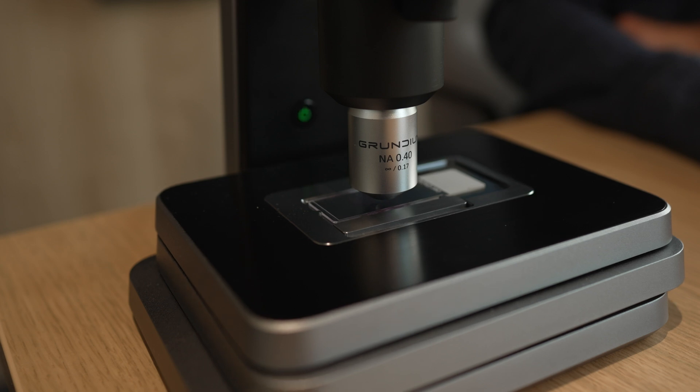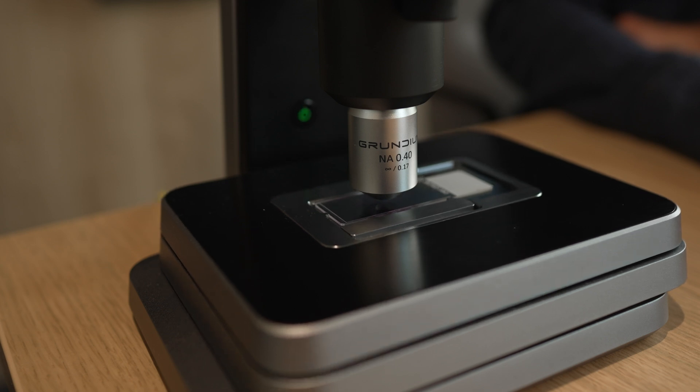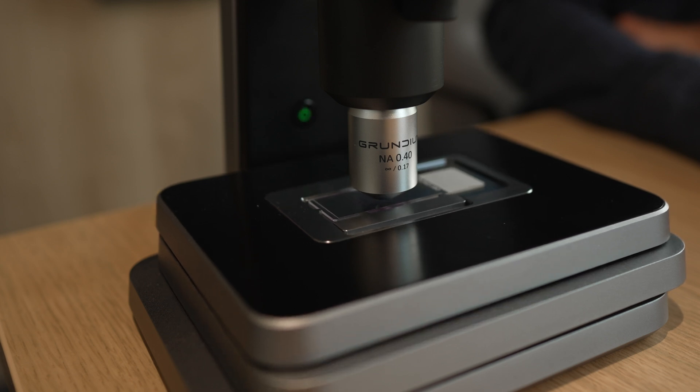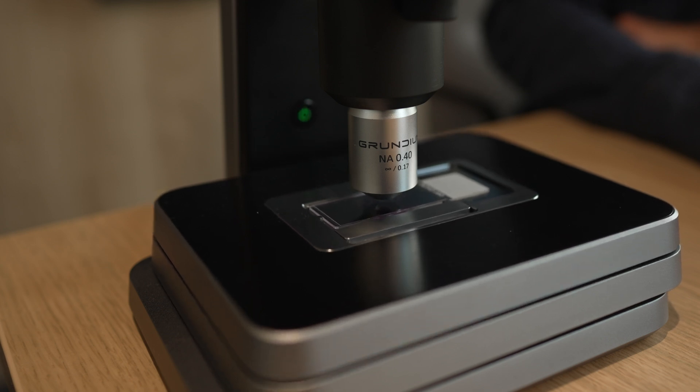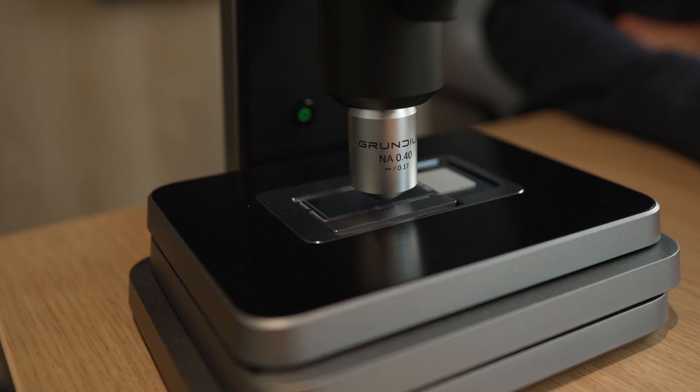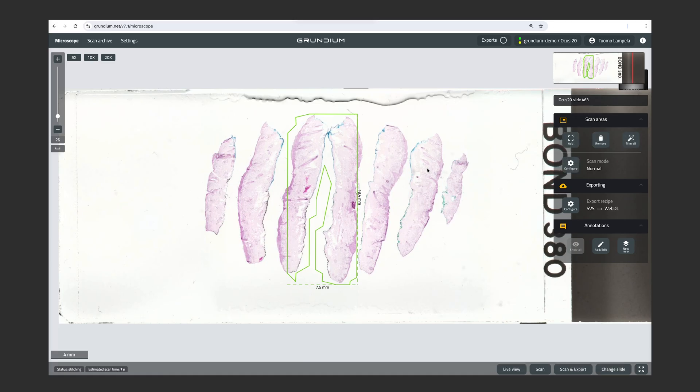The Ocus scans the slide at the optimal layer in focus for each field of view separately and seamlessly stitches the image together. And once the scan area frame turns gray, the scan is finished.